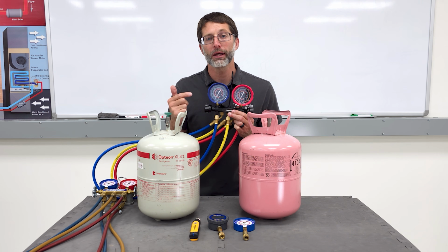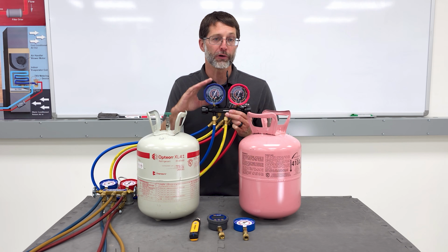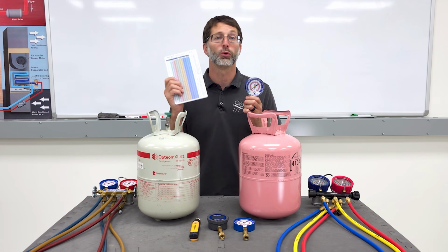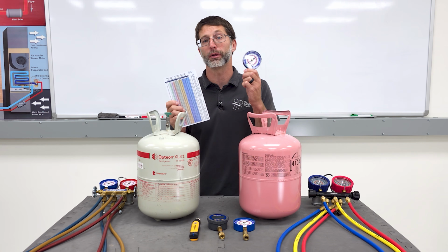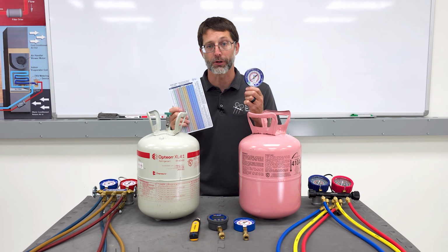If a compound gauge has saturated temperatures of blended refrigerants on the gauge face, a blue low side gauge meant for connecting to the vapor port will typically display the saturated temperatures in dew point. The red high pressure gauge will typically display the saturated temperatures in bubble point. However, a PT chart or app is more accurate to convert the pressure to the correct saturated temperature.